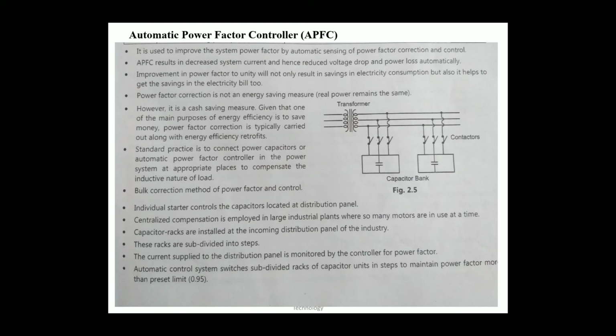You all know that in industry the maximum load is inductive. So the power factor of the industrial or commercial load is lagging. So for improving this power factor, we use the capacitor, that is the capacitor bank. In industry the quantity of capacitors in the bank is maximum, so we use the automatic power factor controller unit, that is an APFC panel.